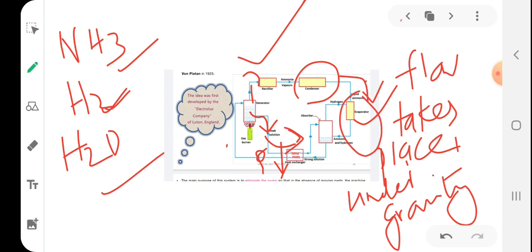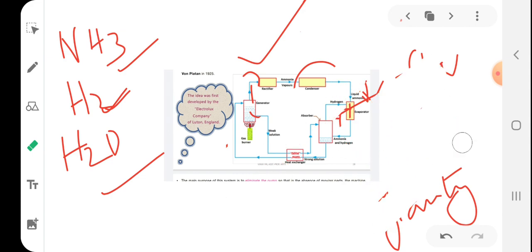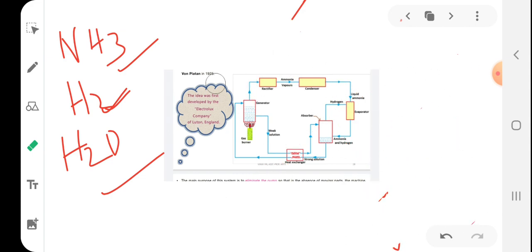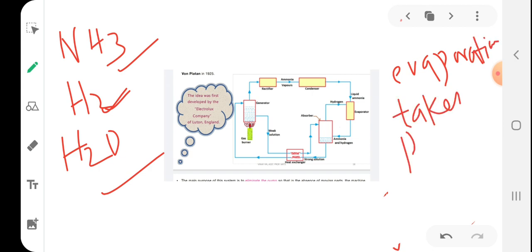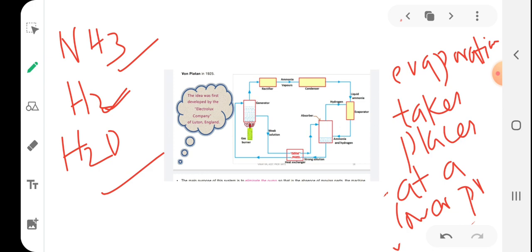So here you can see hydrogen is supplied, right? So what is the function of hydrogen? Actually, hydrogen is a very light gas, so the presence of hydrogen will increase the process of evaporation, right? The hydrogen gas which is fed to the evaporator permits the liquid ammonia to evaporate at a low pressure. So evaporation takes place at a lower pressure due to the presence of hydrogen.